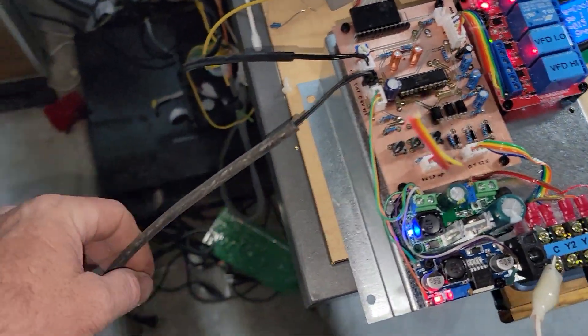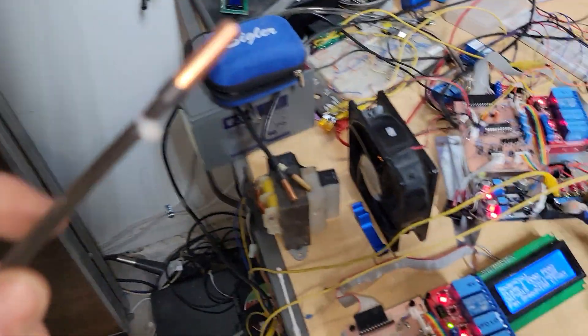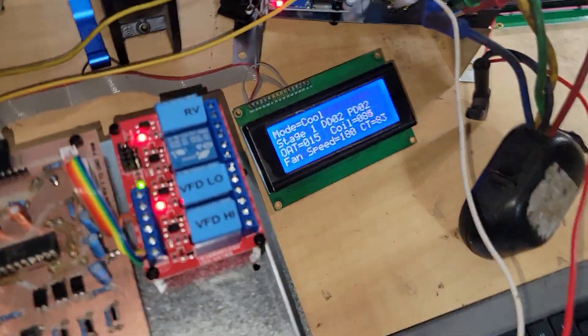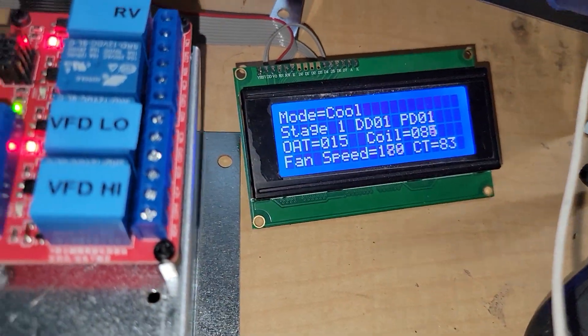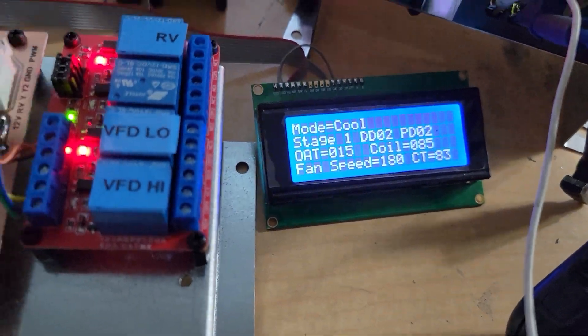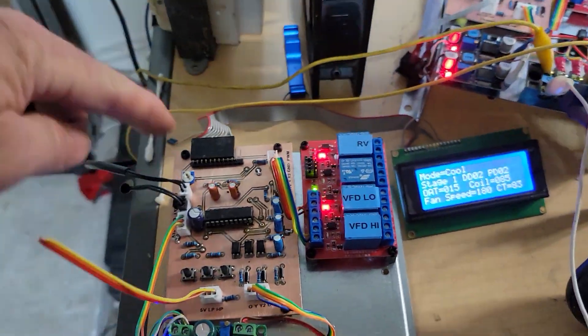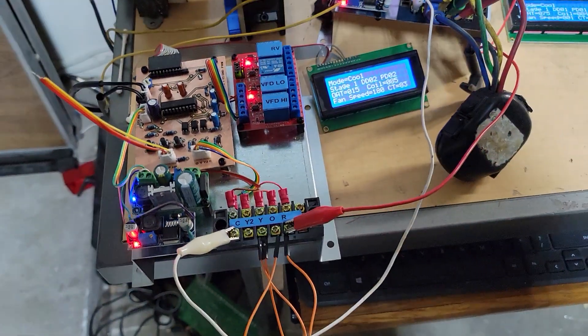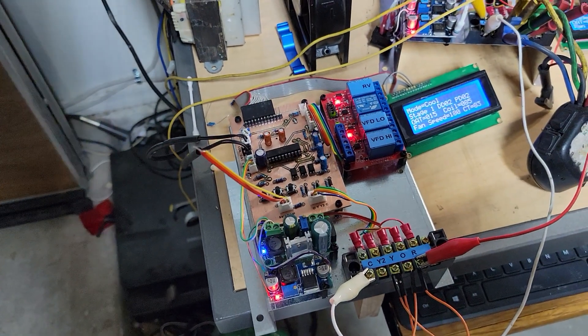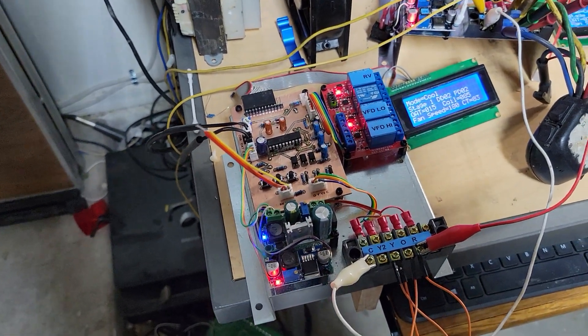This one thermistor here I brought in - evidently it's not a 10k, it must be a 20k because it's like saying 15 degrees on there, which it's not. It says the same thing whichever port I plug it into. I didn't even put my meter on but I just know that's what it is - it's just not a 10k.